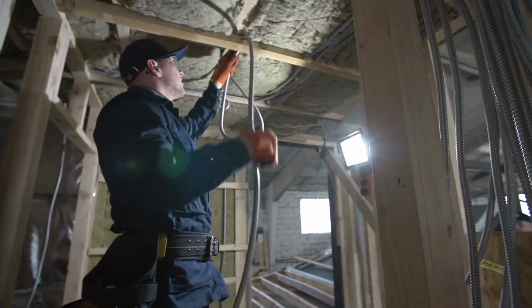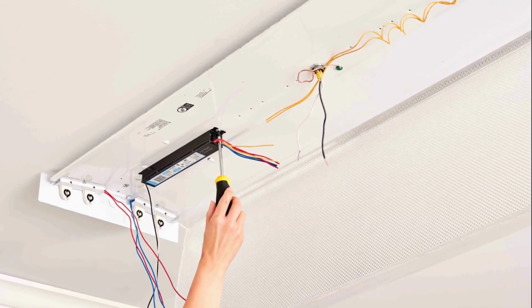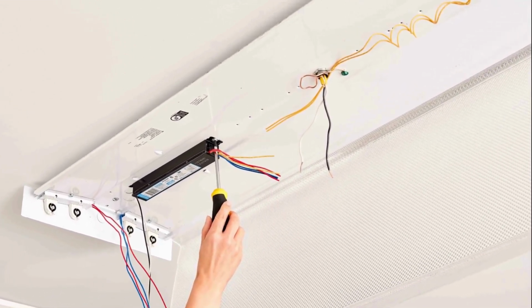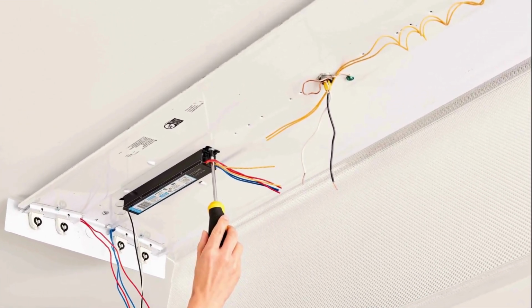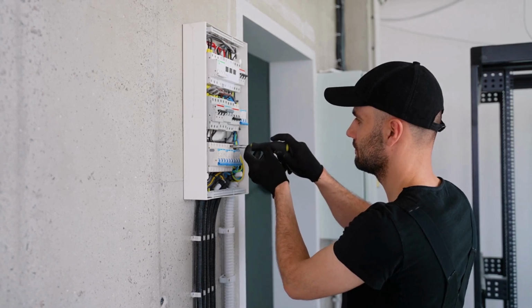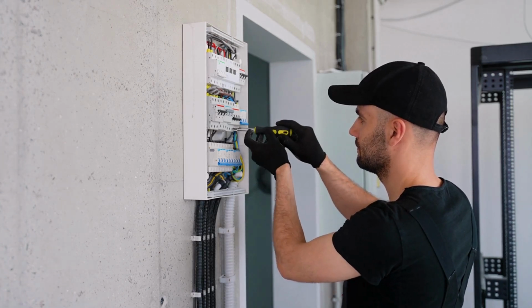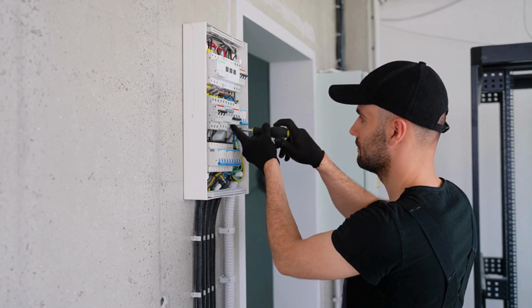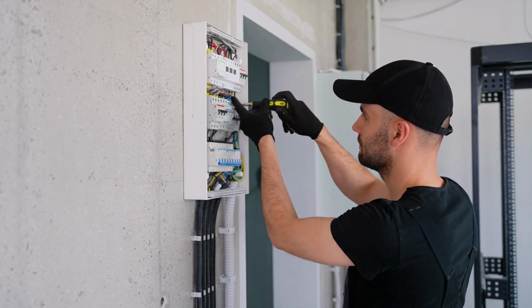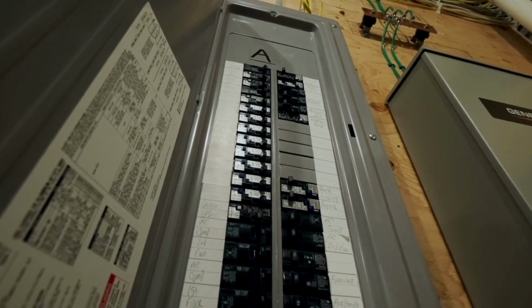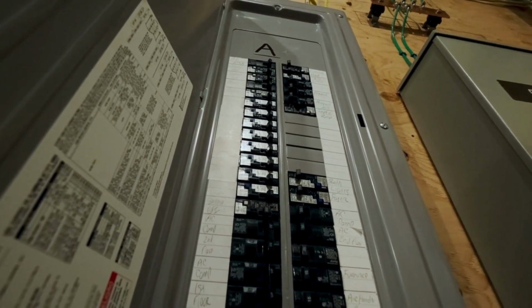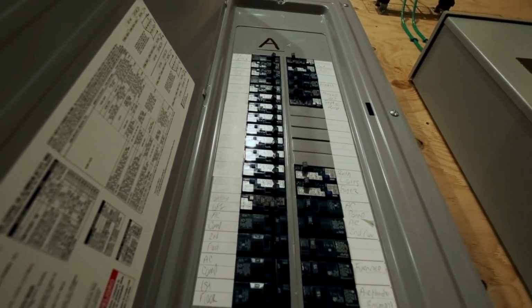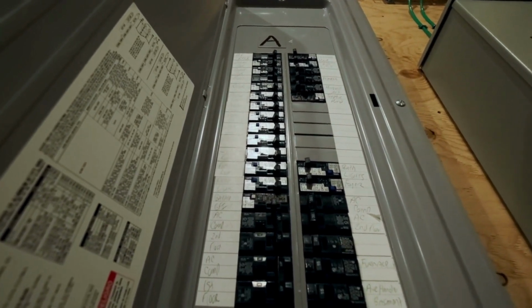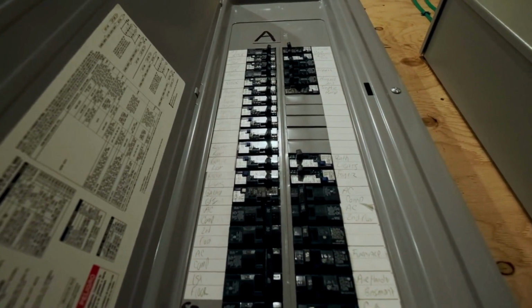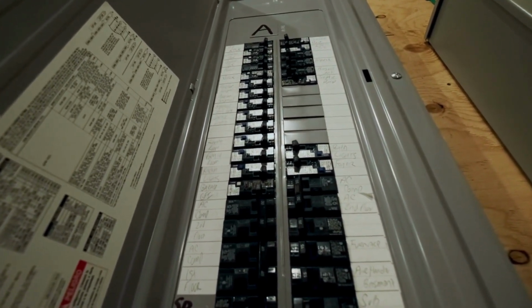Lighting ballasts, especially older ones and high-intensity discharge fixtures, also use capacitors. You'd think a light circuit would be simple and safe once the switch is off, but that ballast capacitor can hold enough charge to give you a serious shock or worse. Same thing with electronic equipment power supplies. Computers, servers, industrial controls, even that innocent-looking power supply on a piece of test equipment can have capacitors that stay charged long after you unplug it.